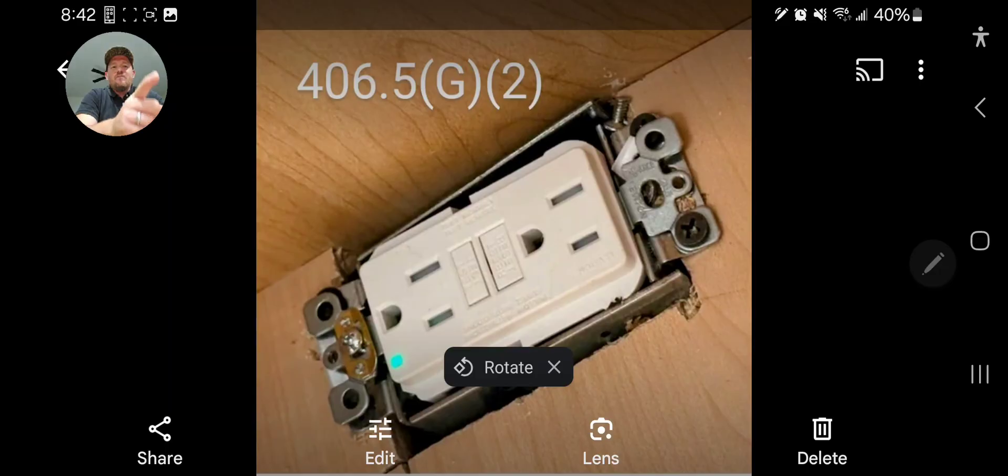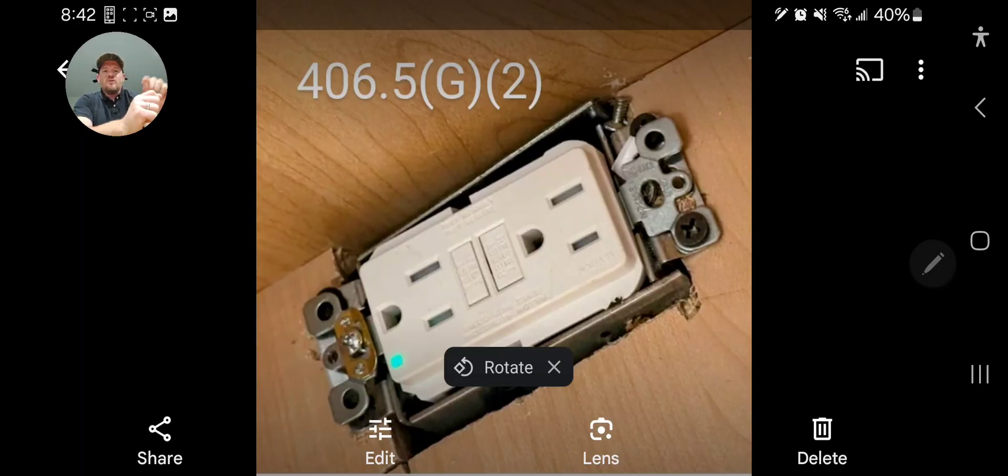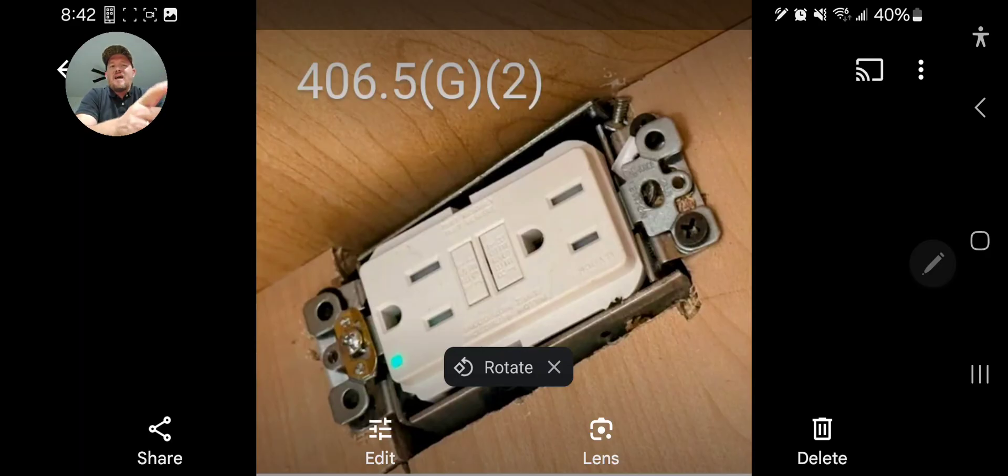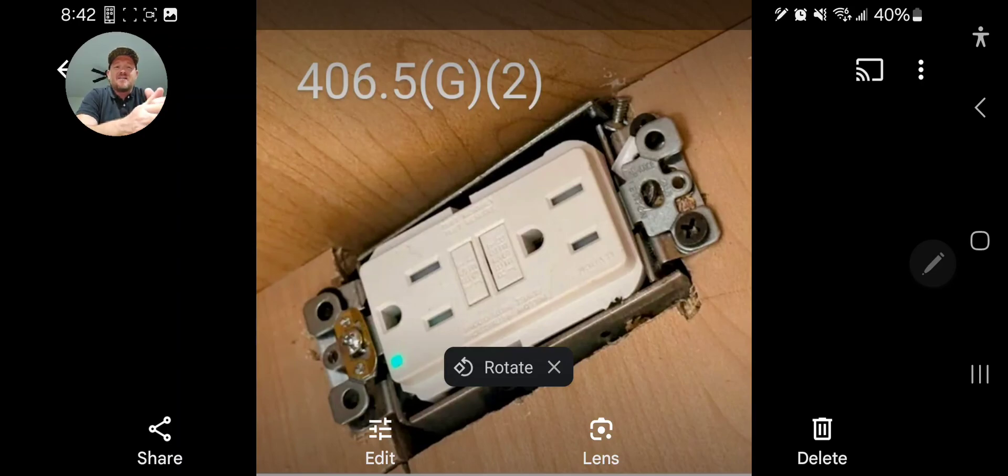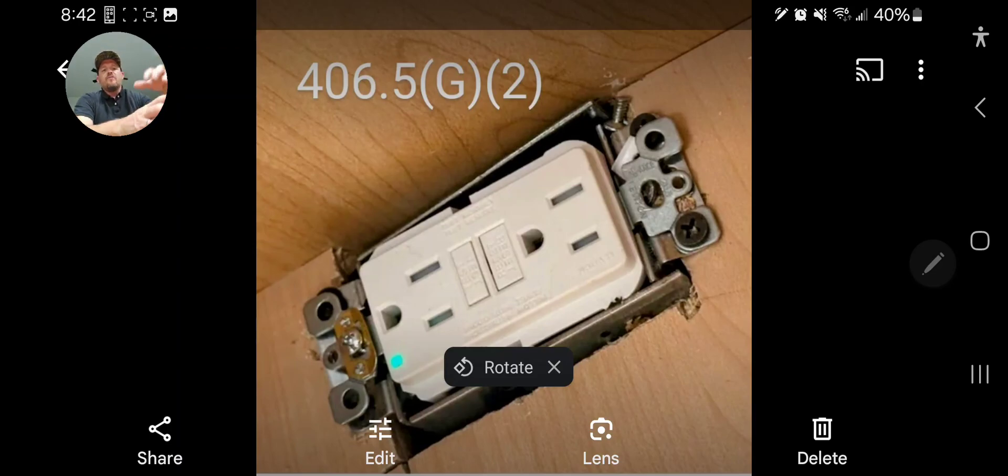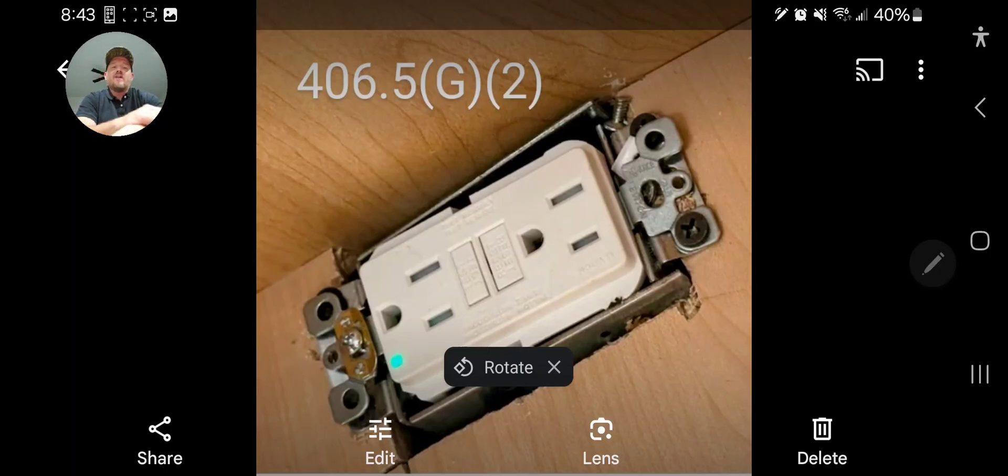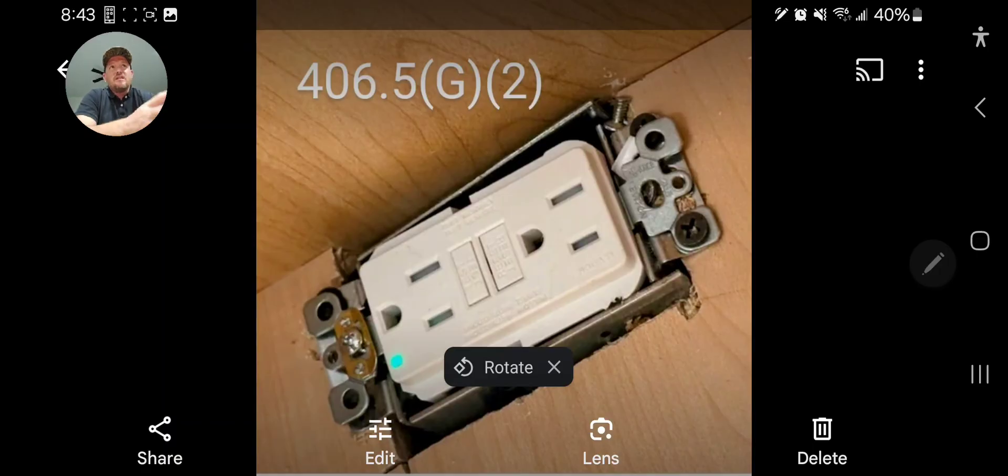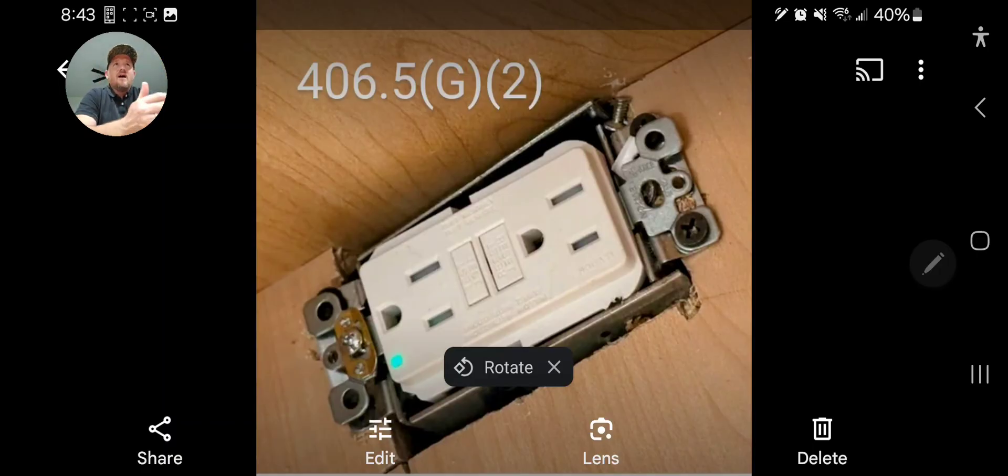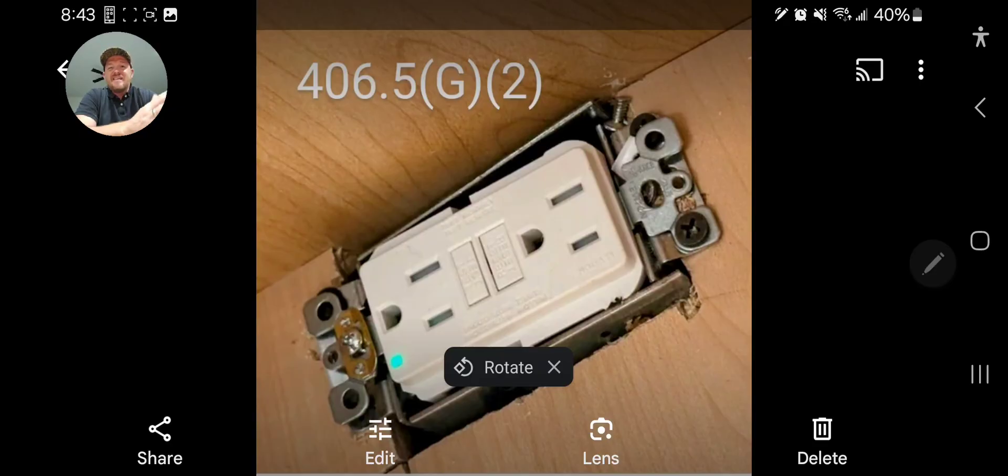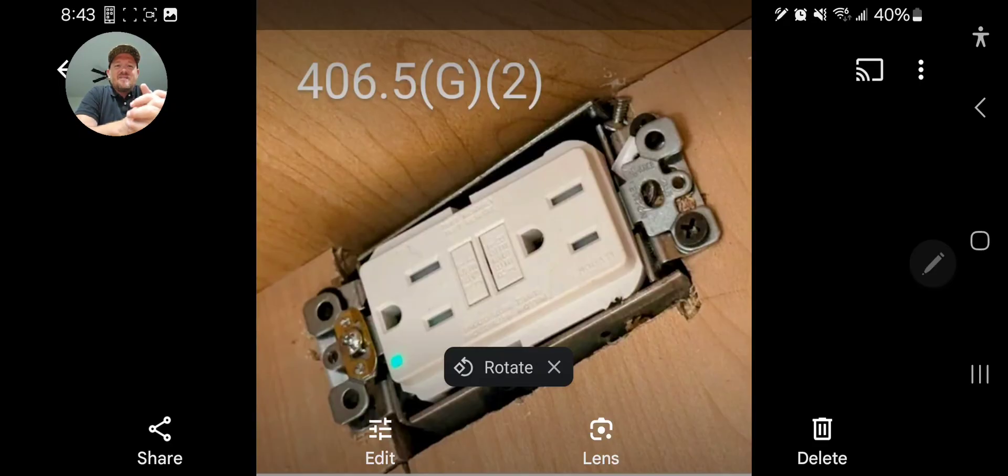it would trip the GFCI so it would kill the load side of the GFCI, but you still have hot conductors likely inside of that box depending on how it was wired. So if you've got water running down in there, yes, you've tripped the GFCI, but you're also creating a bowl for that water to set in, which could potentially leak back up the individual or onto the equipment that it is leaking from.